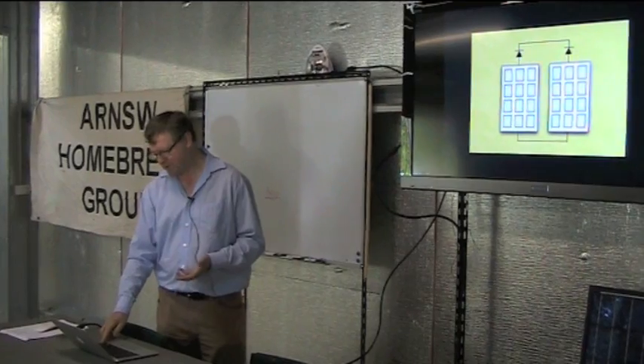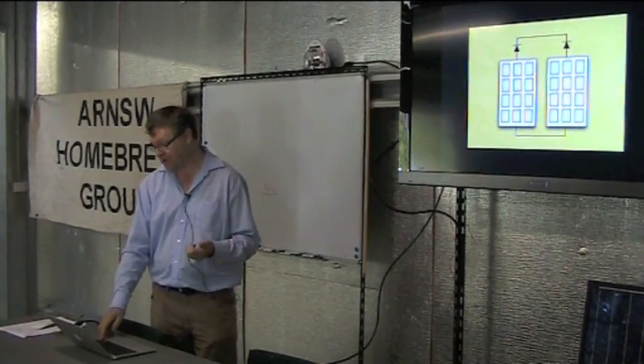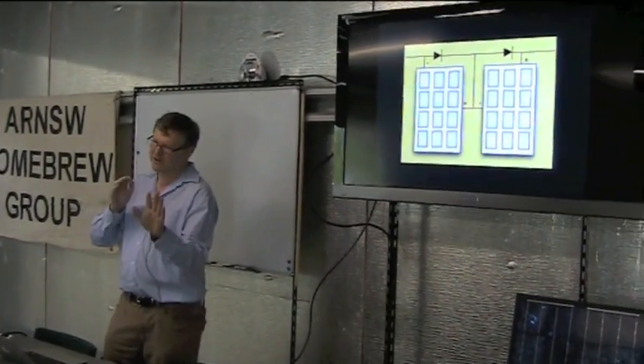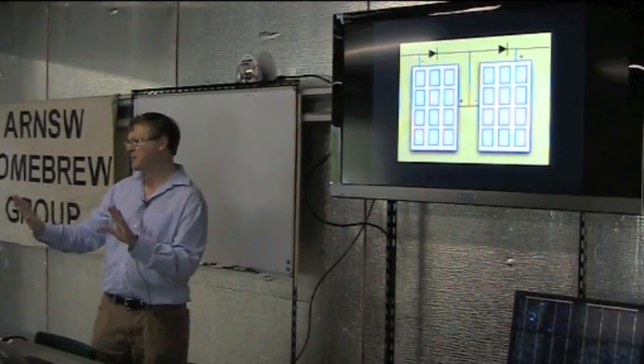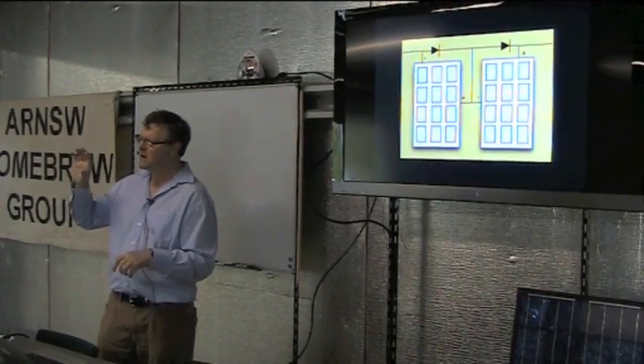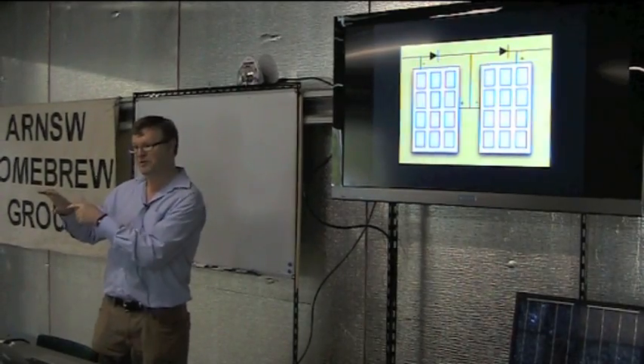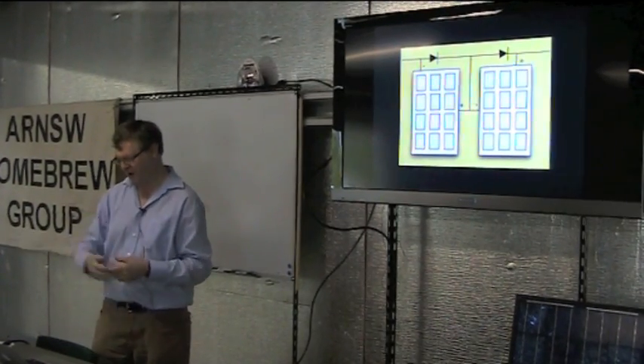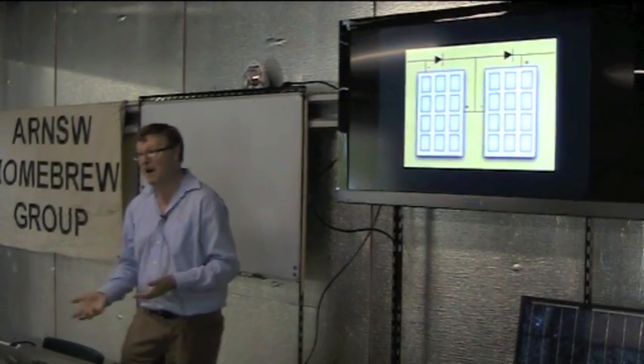If you're going for a higher voltage, you wire panels in series. In that case you might have one illuminated panel with current flowing through one that's not illuminated. A panel with low illumination limits the current that can flow through — it not only doesn't generate power, it actually reduces current. So there are panels that have bypass diodes on them to address this.